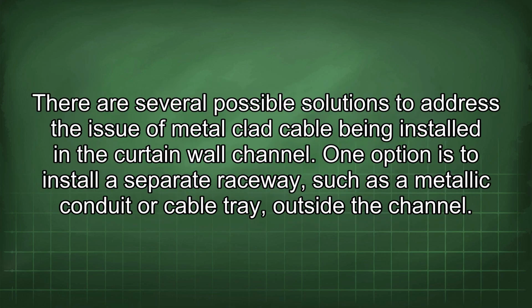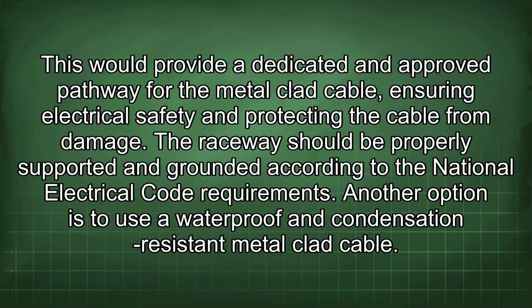There are several possible solutions to address the issue of metal-clad cable being installed in the curtain wall channel. One option is to install a separate raceway, such as a metallic conduit or cable tray, outside the channel. This would provide a dedicated and approved pathway for the metal-clad cable, ensuring electrical safety and protecting the cable from damage. The raceway should be properly supported and grounded according to the National Electrical Code requirements.